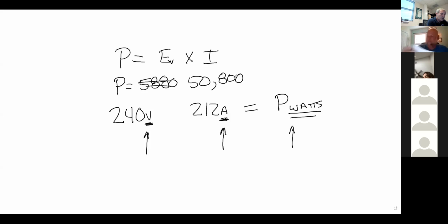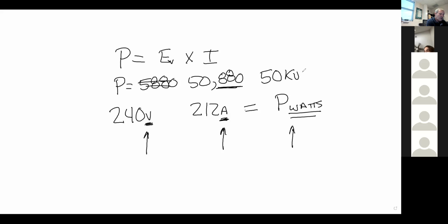I'm just going to throw those numbers out there: 50,880. Got to reference my chart again — there's no such thing as a 50,880 wattage transformer. What's the closest one to it? 50 — 50 kVA. Excellent. 50 kVA, that matches my 50,000 watts. That's close enough to it — even though it's a little bit over, that's minimal, guys. 50 kVA. That one was kind of long there.